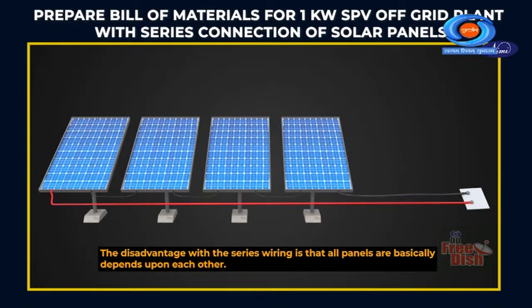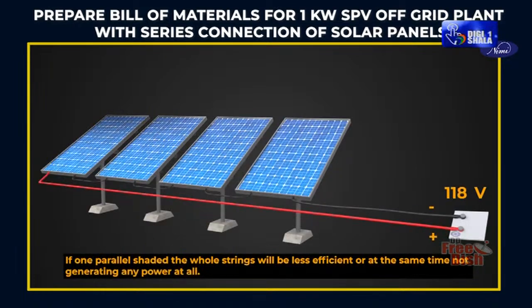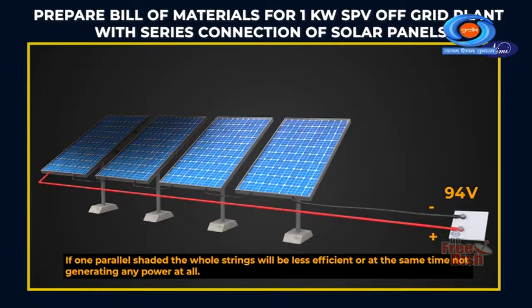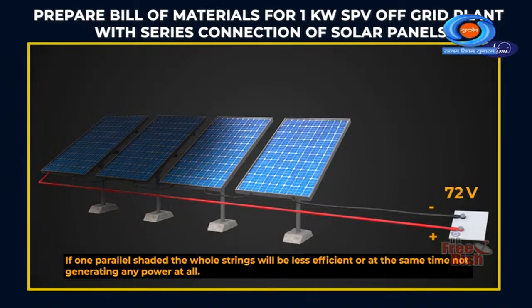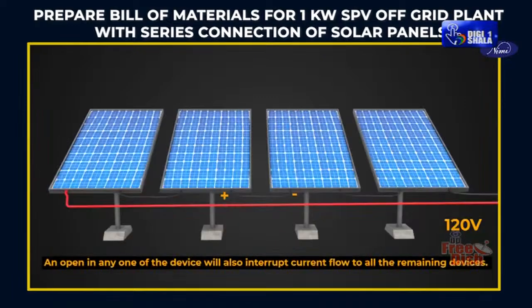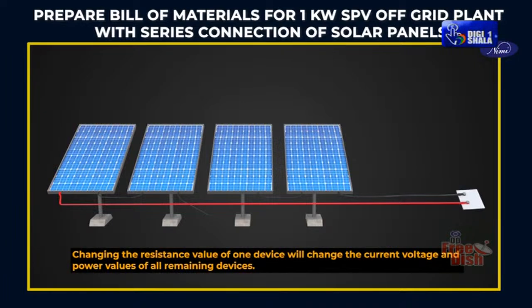The disadvantage with series wiring is that all panels basically depend upon each other. If one panel is shaded, the whole string will be less efficient or will not generate any power at all. An open in any one of the devices will also interrupt current flow to all the remaining devices. Changing the resistance value of one device will change the current, voltage and power values of all remaining devices.